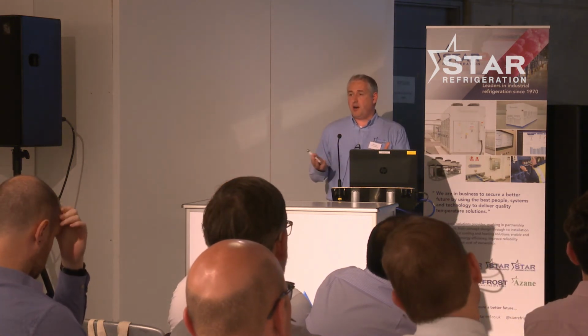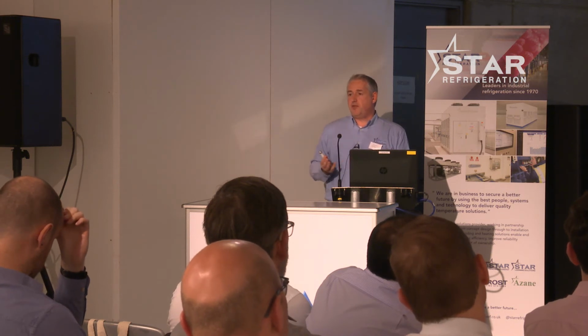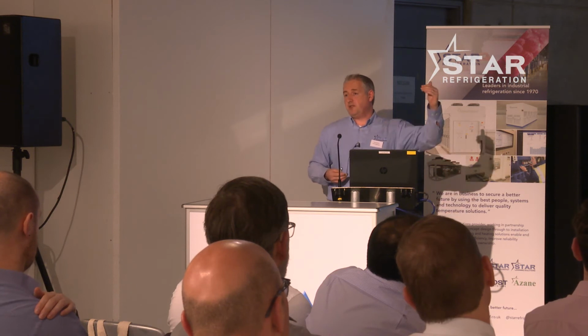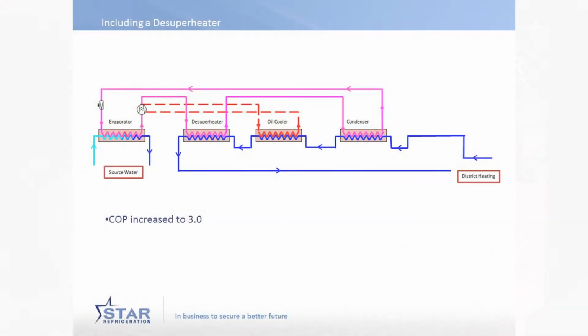Equally though, if we've got two heat pumps, why put them in parallel? Why not put them in series and have one of them heating from 55 to 65 and one heating from 65 to 75? Going back to the earlier bit, one of them is now getting a 10-degree easier journey, an easier hill climb, and that's going to save at least 15% of the efficiency.